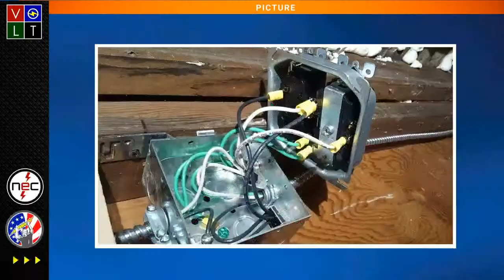I just want to clarify one of my comments from the last thing: that freak drive is what I refer to. It's a VFD, a variable frequency drive. It's a way for the motor to ramp up. They limit the frequency to the motor, and that helps the motor ramp up slower. It extends the motor life, and it also creates a lot less inrush current in your system, and it helps your motor start and stop with less inrush, so you're going to use less current, and it's just going to be a lot more efficient design. But it's a real big compatibility issue with GFCIs, is what we're finding out.